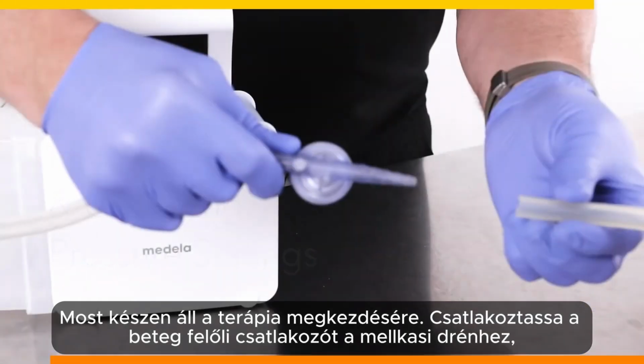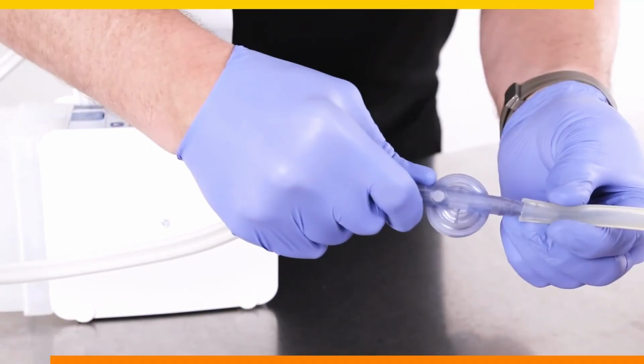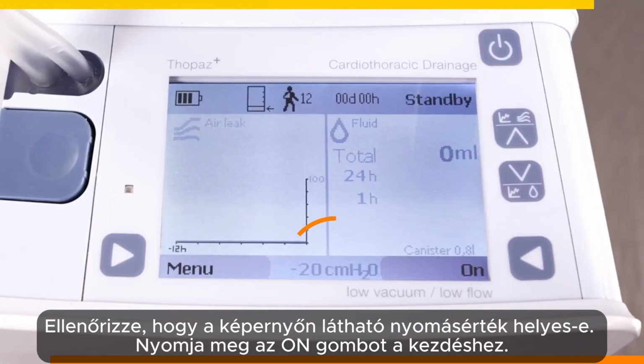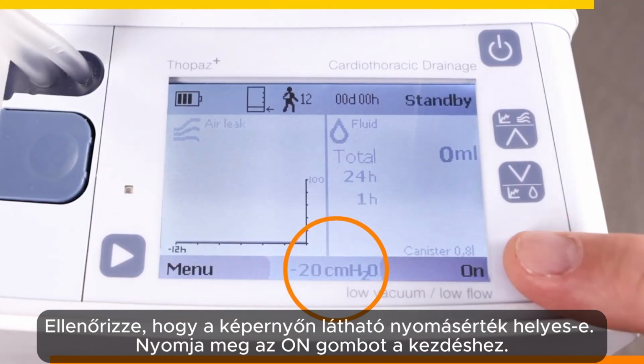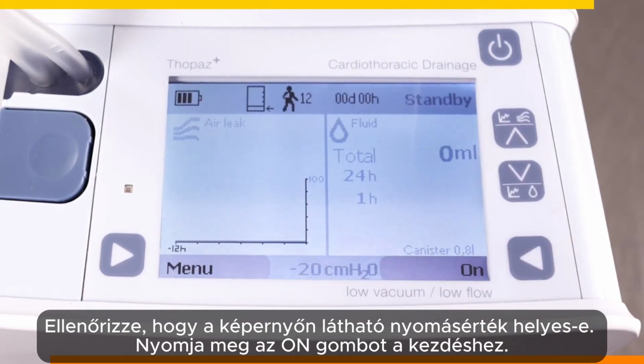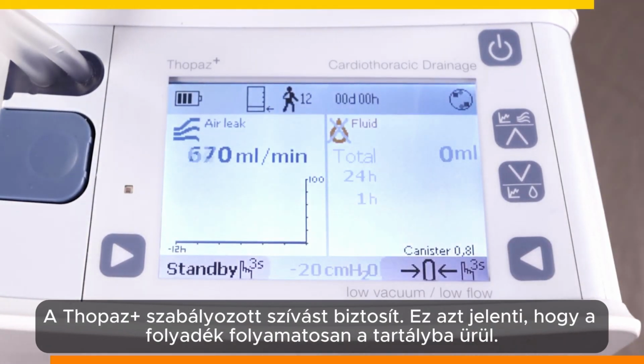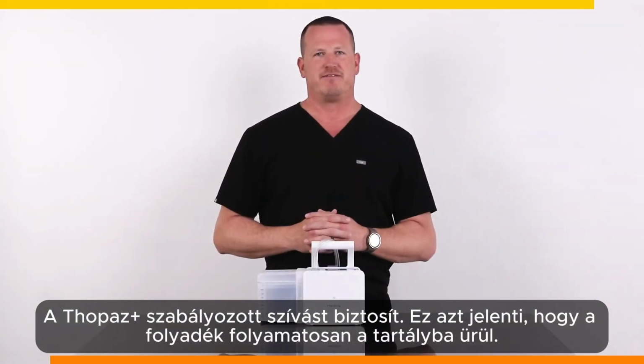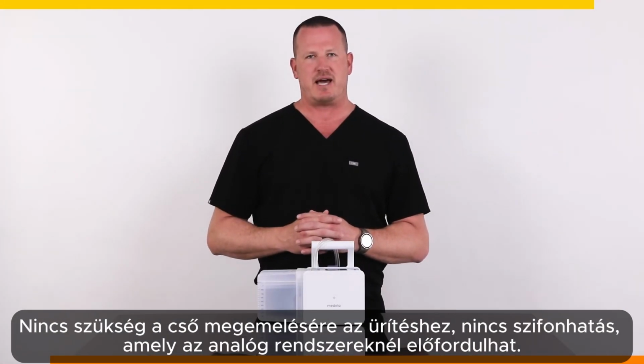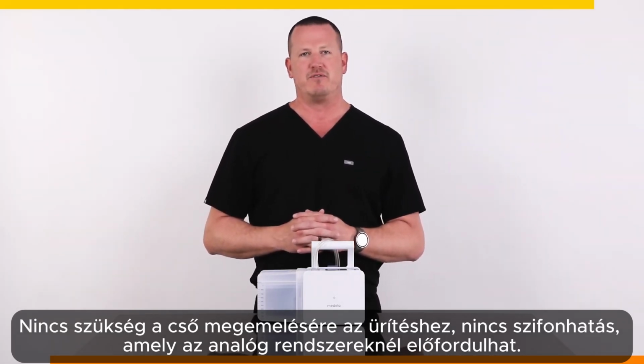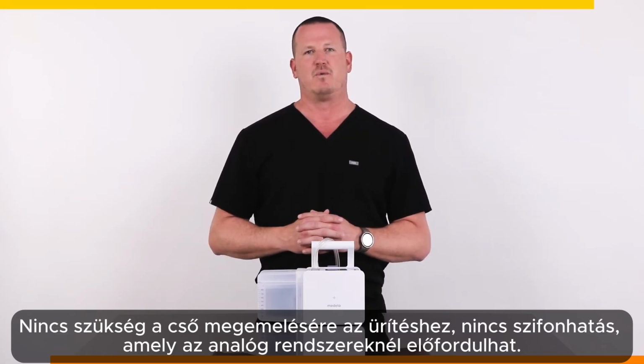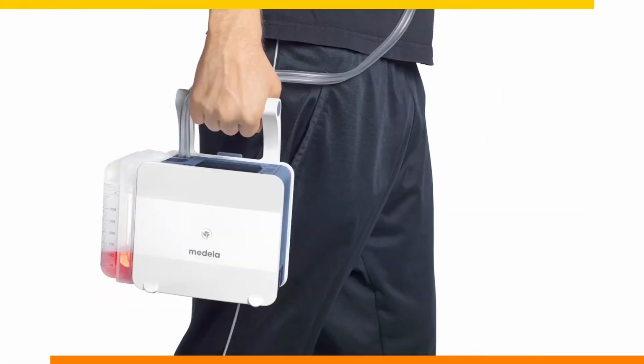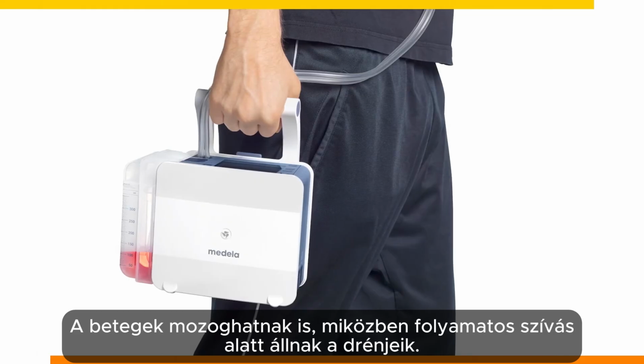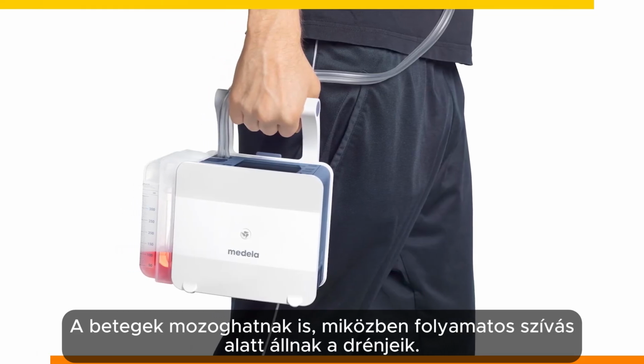Connect the patient connector into the chest tube and ensure that the pressure on the bottom center of the screen is correct. Press on to begin. The Thopaz+ provides its own battery-powered regulated suction source. This means that fluid will always be draining into the canister, and there is no need to pick up the tube to drain it, thereby removing the siphon effect that can occur with analog systems. Patients can also mobilize while having continuous suction applied to their drains.